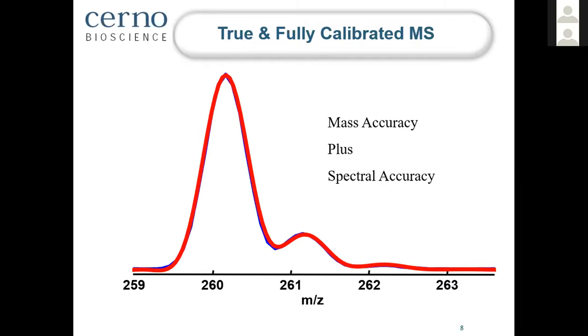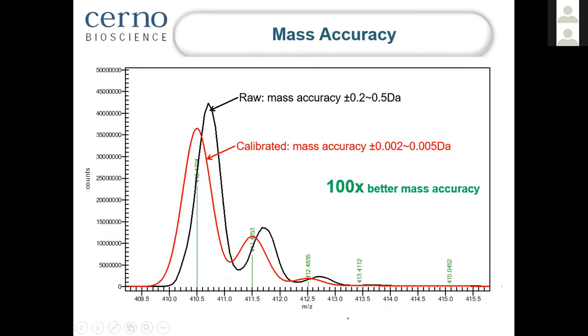And thereby we achieve both mass accuracy and spectral accuracy. Because of the calibration we perform, we correct the mass shift between the raw data and the calibrated version. That shift can be quite significant on a quadrupole system, on the order of 0.X decimal point. But after calibration, we can move it to the correct location and thereby increase the mass accuracy by a factor of 100, to the third decimal point, to 0.00X.